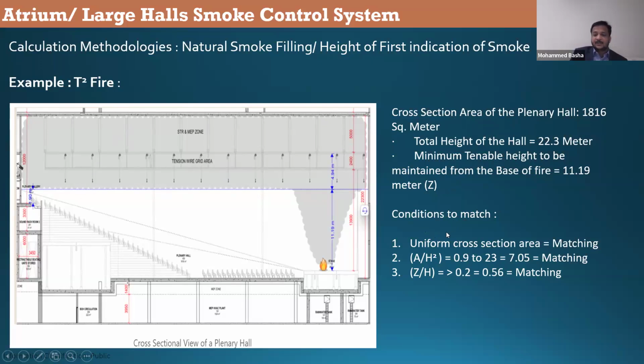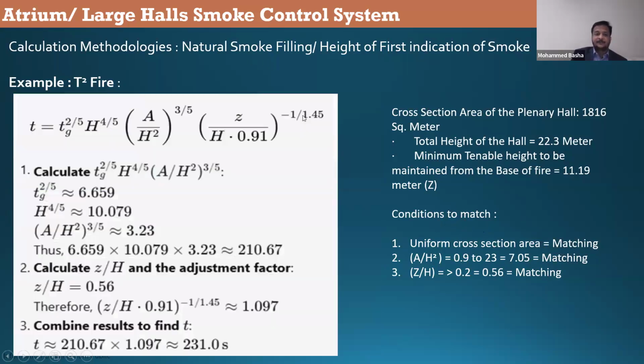Conditions to match. For the T-square fire, we had 5 conditions basically. It should be a uniform cross section. The A by H square must be 0.9 to 23. Z by H shall be greater than 0.2. In this example, I am matching all the scenarios. So first you need to check whether you are matching these conditions or not, then move on to the formula. If you are not matching any one of these conditions, then you cannot use the natural smoke filling methodology.